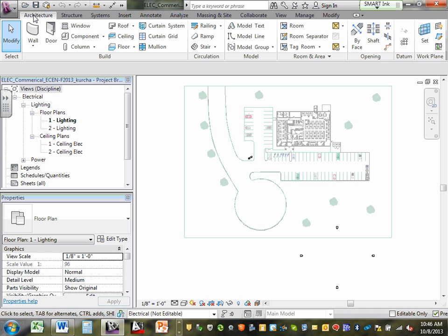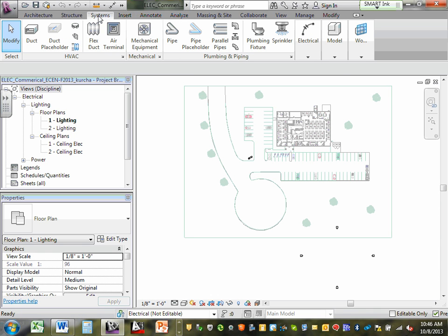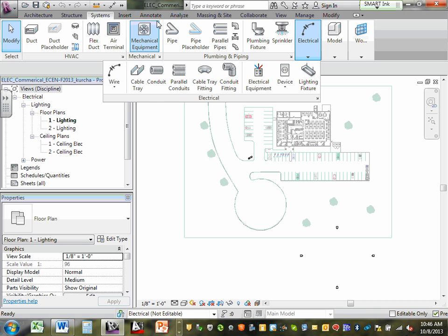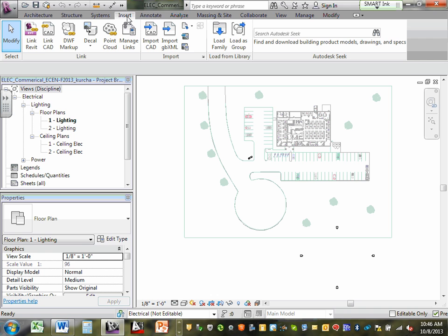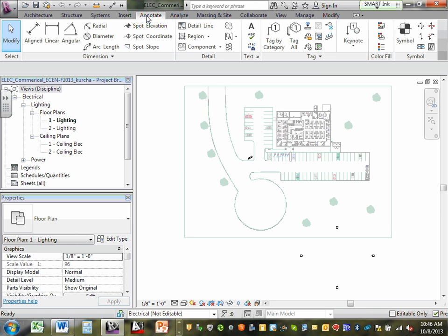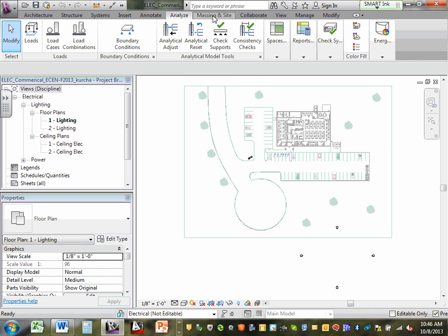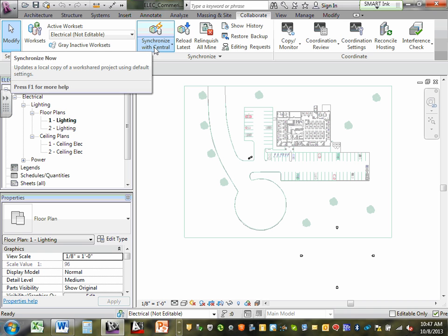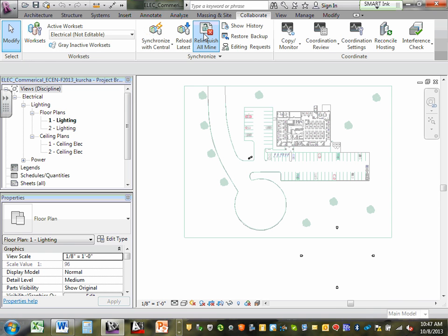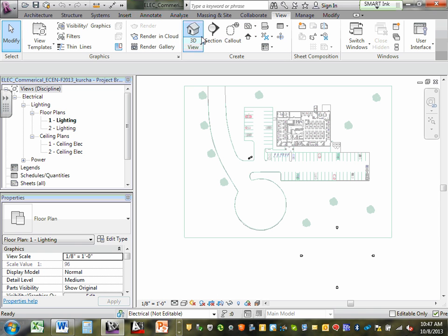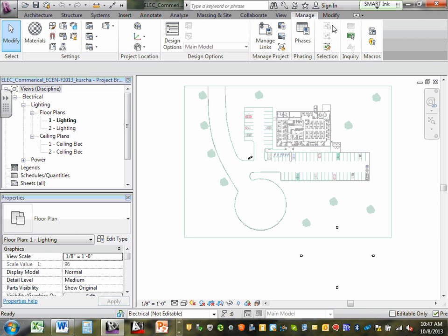To repeat: it defaults to Architectural and Structural first. Systems is where you need to be — Systems and Electrical. Insert gets you CAD files into Revit and handles linking. Annotation gets you tags next to your equipment and receptacles. Collaborate is where you synchronize with central and reload. Relinquish — every time you touch something in Revit, it assigns you to that thing, so if you want others to move it, go Relinquish All Mine when you leave the project.